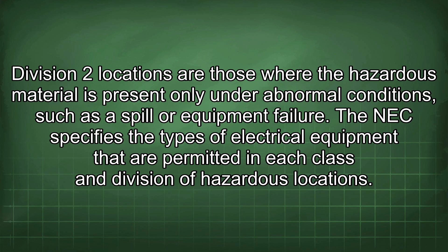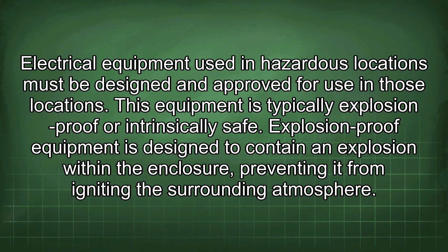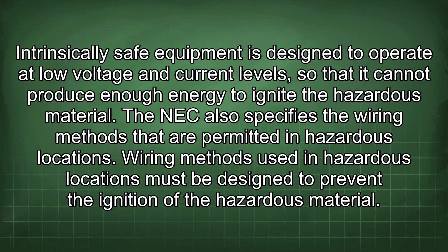The NEC specifies the types of electrical equipment that are permitted in each class and division of hazardous locations. Electrical equipment used in hazardous locations must be designed and approved for use in those locations. This equipment is typically explosion-proof or intrinsically safe. Explosion-proof equipment is designed to contain an explosion within the enclosure, preventing it from igniting the surrounding atmosphere. Intrinsically safe equipment is designed to operate at low voltage and current levels so that it cannot produce enough energy to ignite the hazardous material. The NEC also specifies the wiring methods that are permitted in hazardous locations. Wiring methods used in hazardous locations must be designed to prevent the ignition of the hazardous material.